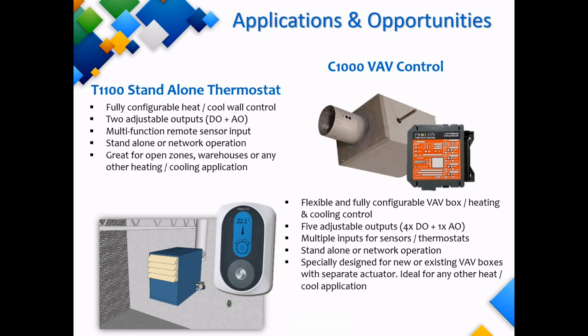We also offer another VAV controller, the C1000 VAV. You will notice that this controller does not have an integrated actuator. It is usually used in retrofit applications where the contractor wants to reuse existing actuators, whether they are floating or modulating. Since it has 4 digital outputs and 1 analog output, it is able to control an external actuator and still have additional outputs for reheat, fan-powered boxes, and so on.